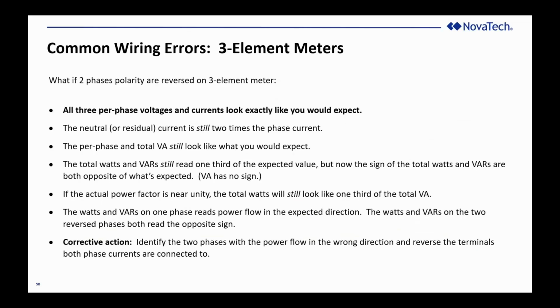So what happens if I reverse two phases on the three element meter and only one of the phases has the polarity correct? Well, think about it. What I've just done is I've reversed the direction of the entire power with only one element pointing in the opposite direction. So this is going to look very much like one phase with reverse polarity, except everything's going in the opposite direction. So voltage and current still looks normal. Residual current is still 2 times the phase current. The per phase and total VA still look like you'd expect. The watts and VARs still read 1/3 of the expected value. The watts is about 1/3 of the VA if you have good power factor.